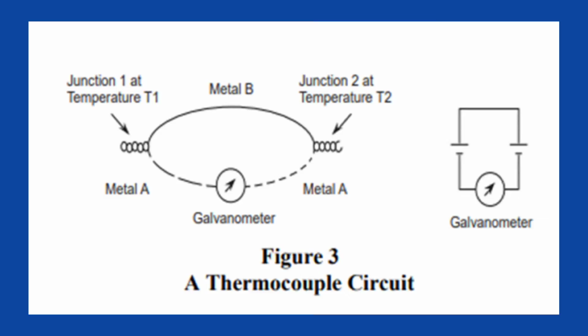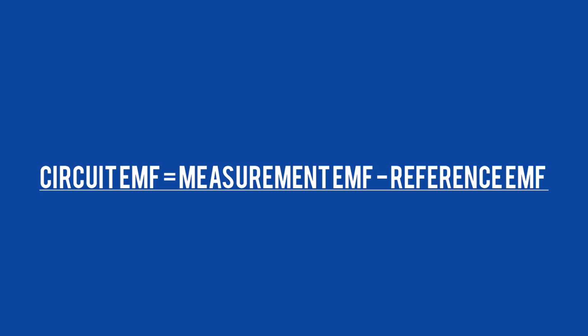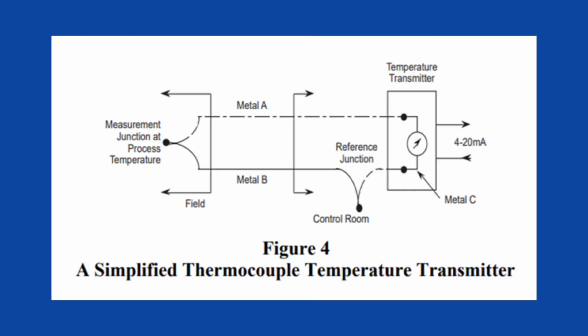The relationship between total circuit voltage and the EMF at the junction is: circuit EMF equals measurement EMF minus reference EMF. If the circuit EMF and reference EMF are known, measurement EMF can be calculated and the relative temperature determined. To convert the EMF generated by a thermocouple to the standard 4 to 20 milliampere signal, a transmitter is needed. This kind of transmitter is called a temperature transmitter. Figure 4 shows a simplified temperature transmitter connection.